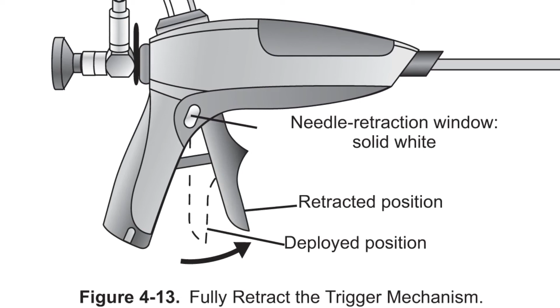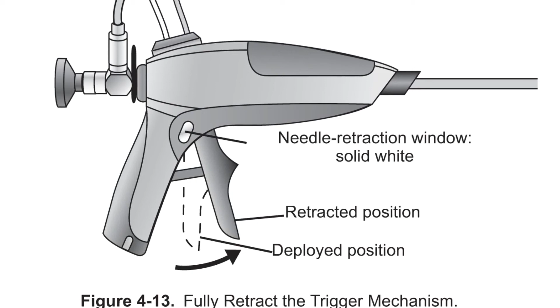To fully deploy the needles and retract the shields, firmly pull back the trigger mechanism until the trigger reaches the automatic stop. The needles and shields deploy together. The shields retract slightly to prevent tenting. An audible snap will be heard and a click may be felt, which means the needles and shields have been properly deployed. Confirm the handpiece is flush against the urethra wall.